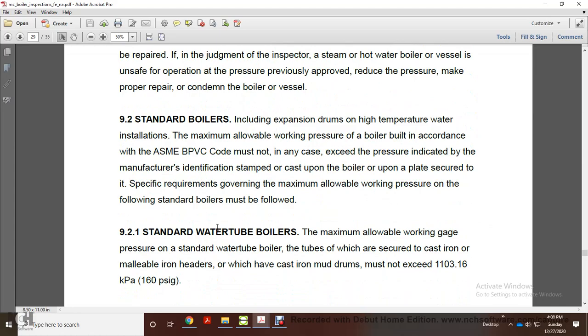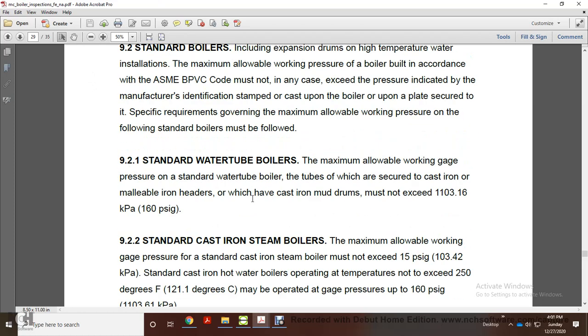9.2 Standard boilers include the expansion drum of the high temperature water boiler. The maximum allowable working pressure of boilers built in accordance with the ASME code must not exceed the pressure indicated by the manufacturer's identification stamp cast upon the boiler or upon the plate secured to it. The following requirements governing maximum allowable working pressure on standard boilers must be followed.